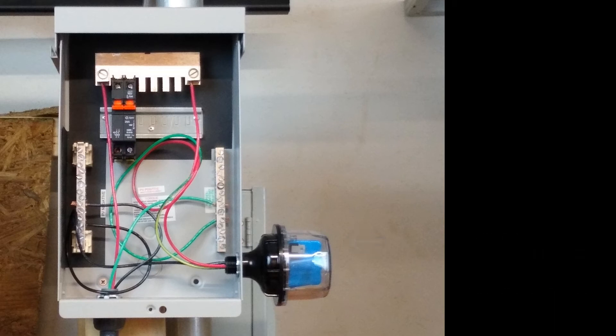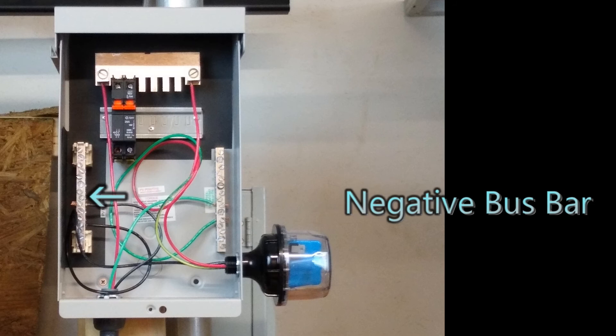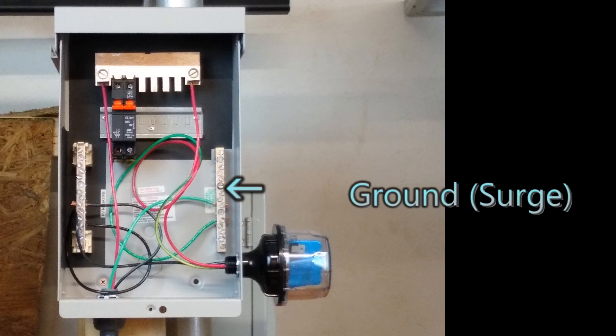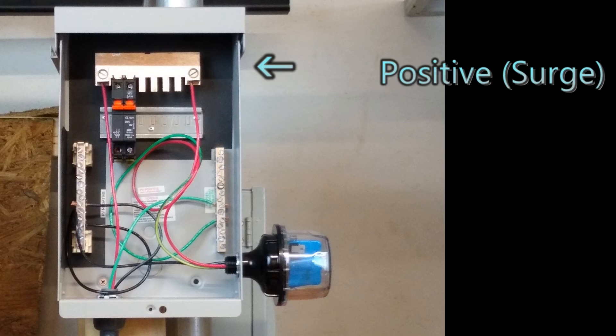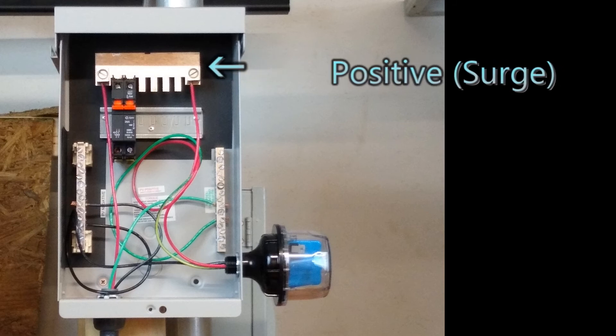So this is a midnight solar surge protection goes through one of the knockouts on the side of the box. So then it connects in three points. It has a negative wire, which connects to the negative bus bar. It has a ground wire, which connects to the ground bus bar. And then it has a positive wire and you want to connect that up on the PV output circuit. That will protect all of your source circuits.